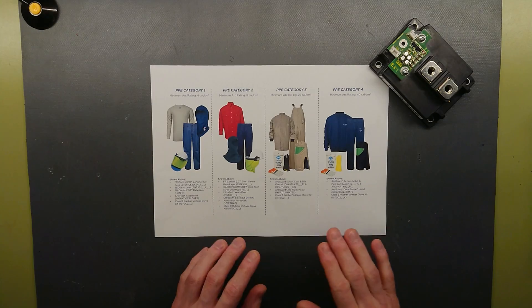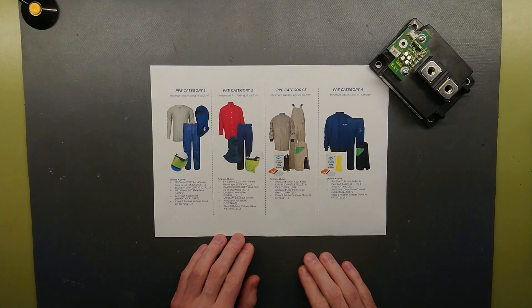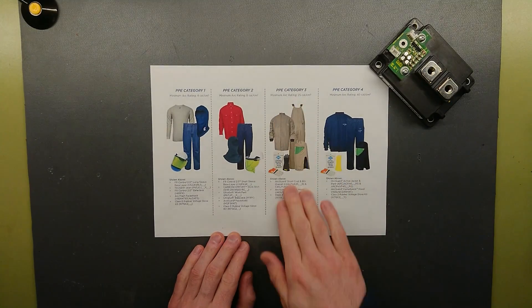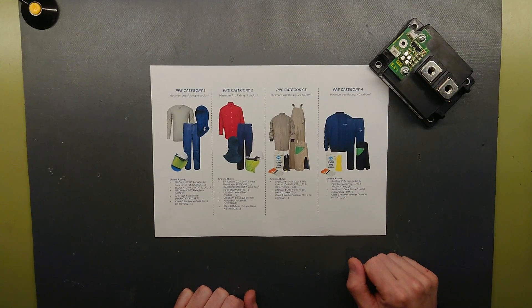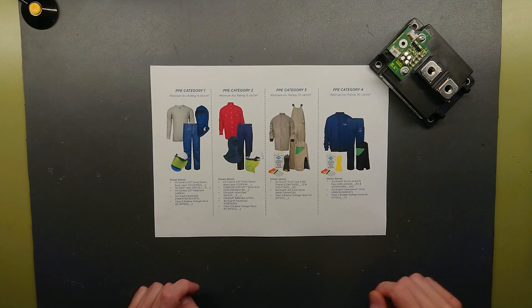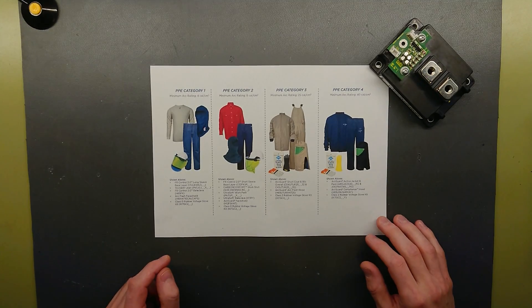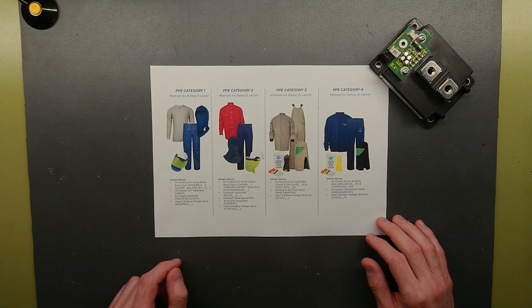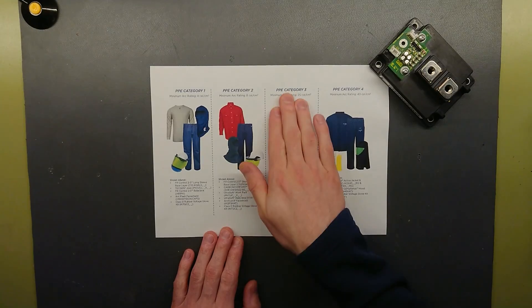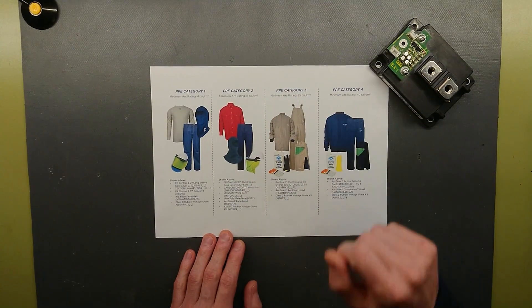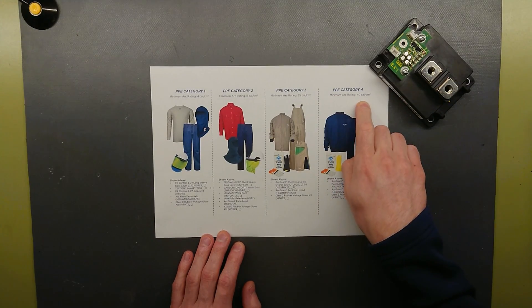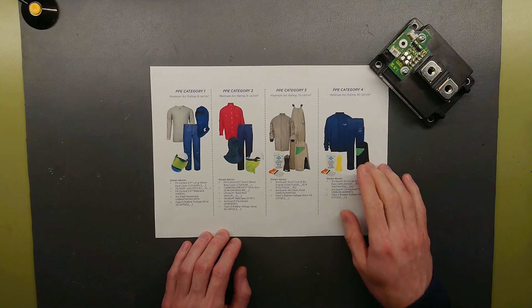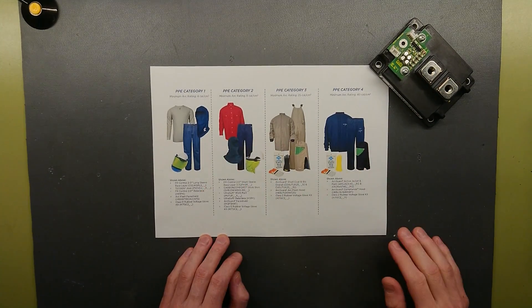A more recent approach I have seen in the industry is that we are moving from PPE category 3 to category 2 by installing current limiting fuses or breakers. If I had to go into some kind of breaker room with typically 3 or 6 kV transformers, motors and breaker circuits, I would have been forced into wearing category 3 or category 4 at worst due to the high arc calories per square centimeter rating.